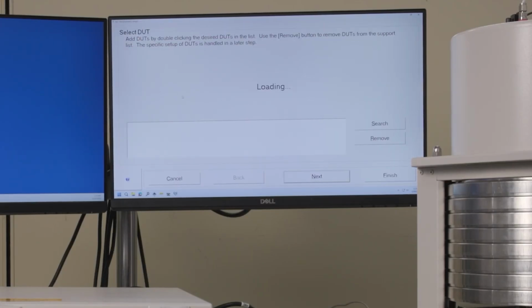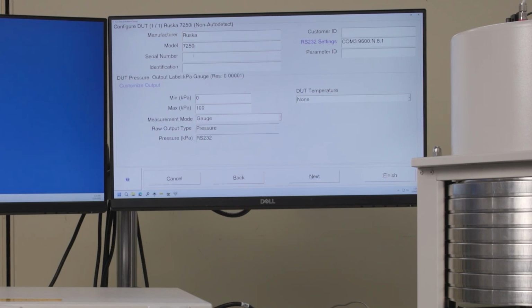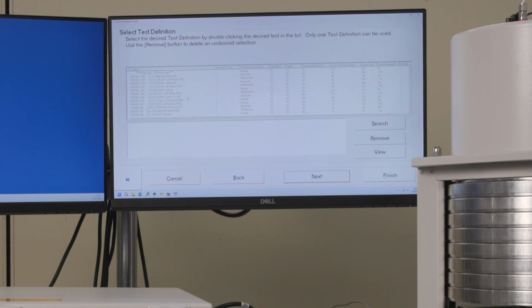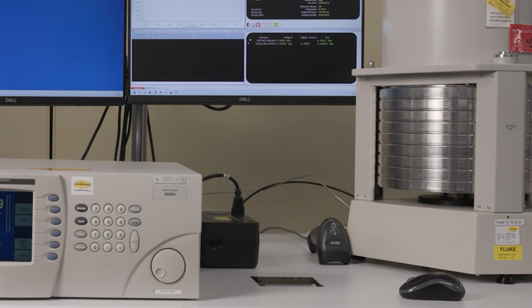Next, we configure the calibration using Compass. The DUT's serial number and maximum pressure are entered, followed by selecting the test type and pressure mode, gauge mode in this case. Compass automatically reads the piston, cylinder, configuration, and mass set. These elements define the pressure standards used in calibration. The calibrator loads weights based on the target pressure.